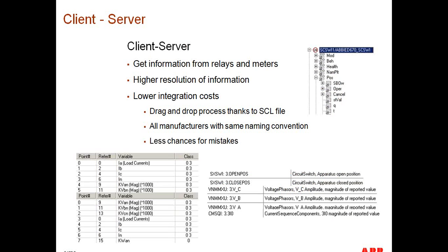Second part that's very important to understand about the standard is Client-Server. This is a protocol that allows us to exchange information from our IEDs up to higher level systems such as an HMI, gateway, or a remote terminal unit. And thanks to our naming convention, this allows us to perform our engineering in a much more expedited way.